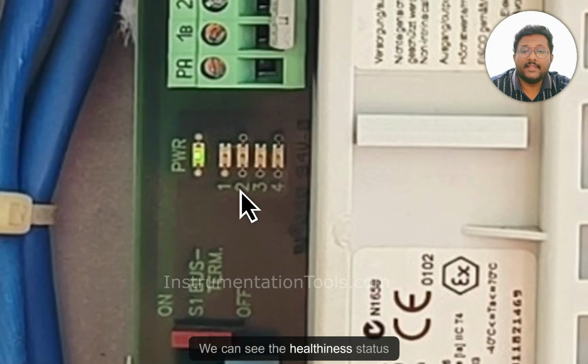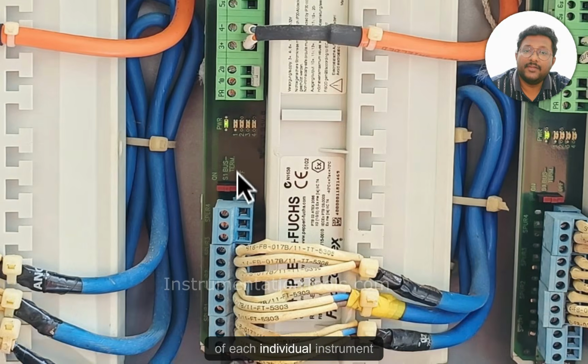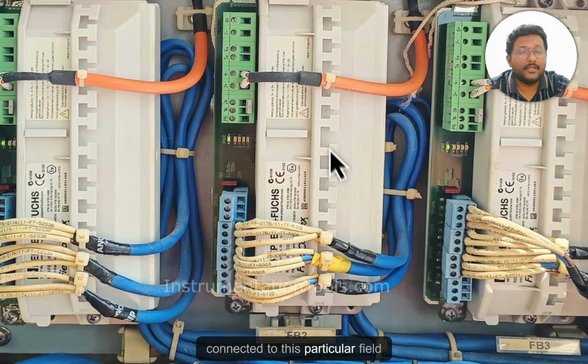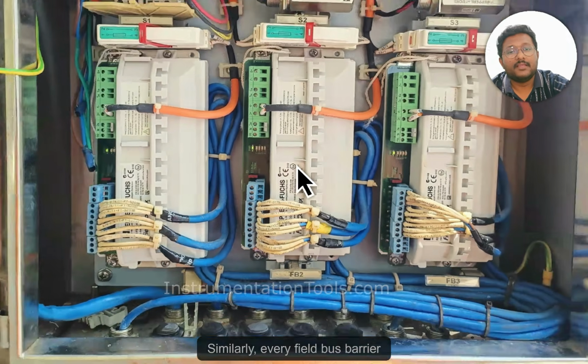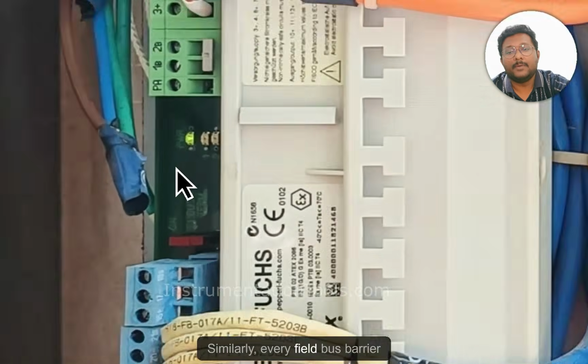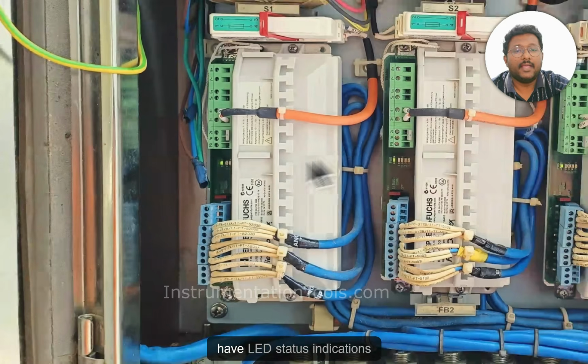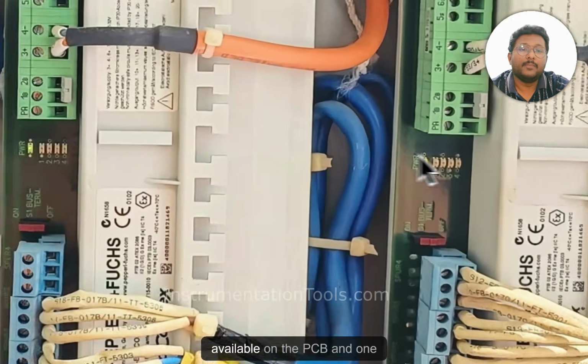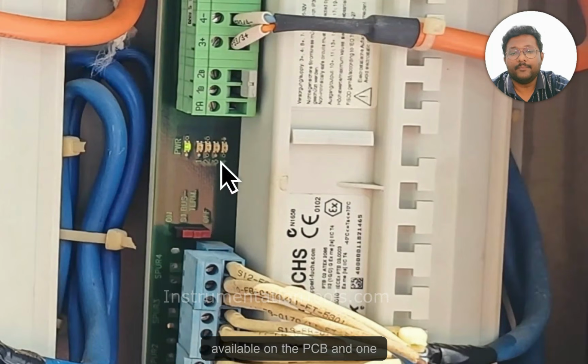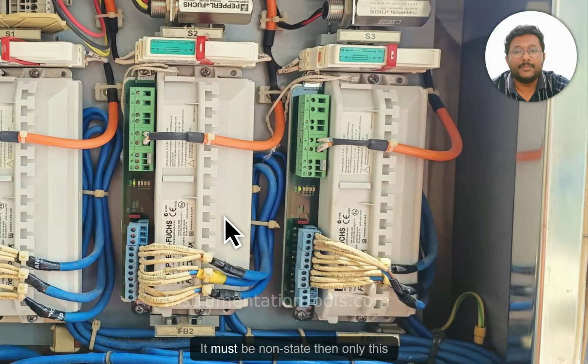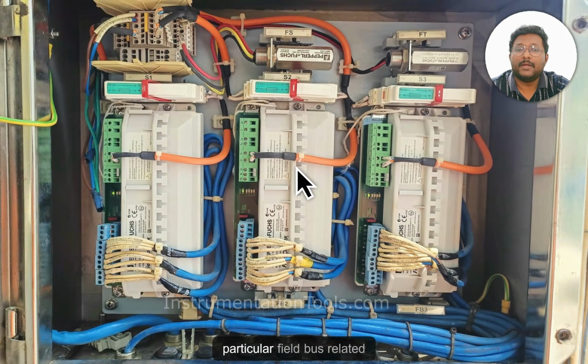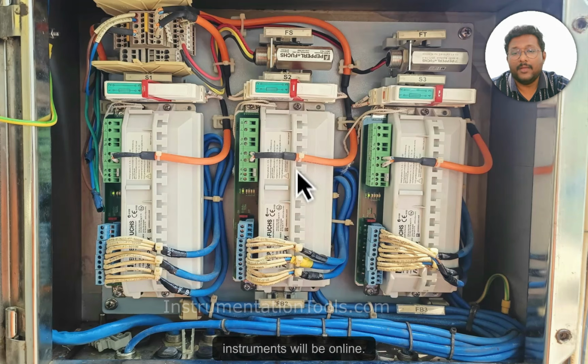We can see the healthiness status of each individual instrument connected to this particular field bus barrier. Similarly, every field bus barrier has LED status indications available on the PCB, and one terminate on-off switch is also available. It must be in the on state, then only the instruments related to this particular field bus barrier will be online. Otherwise, they will not work.